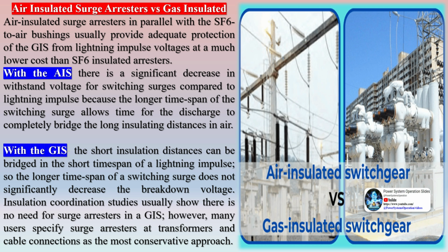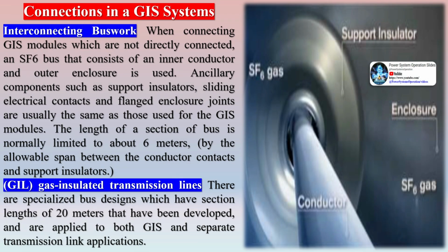Insulation coordination studies usually show there is no need for surge arresters in a GIS. However, many users specify surge arresters at transformers and cable connections as the most conservative approach.